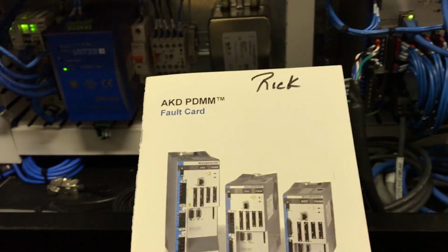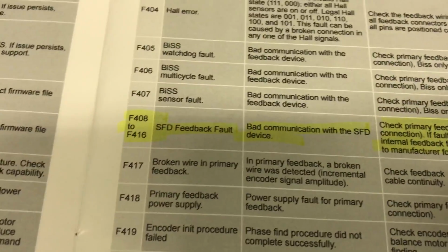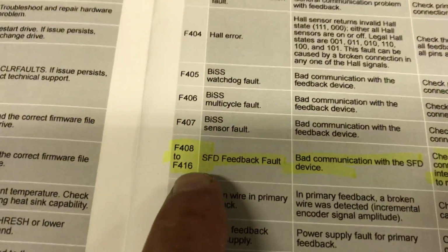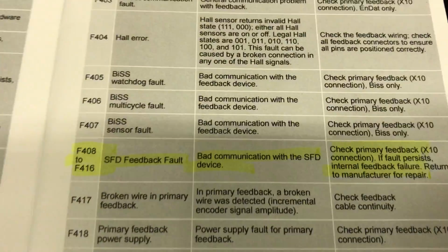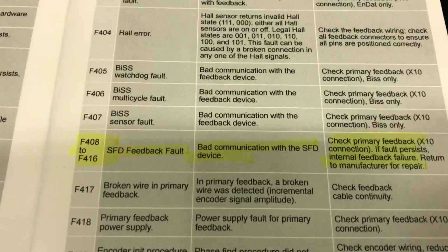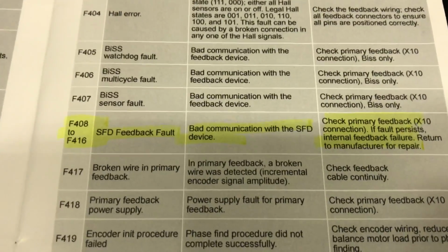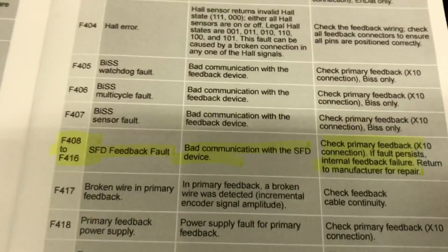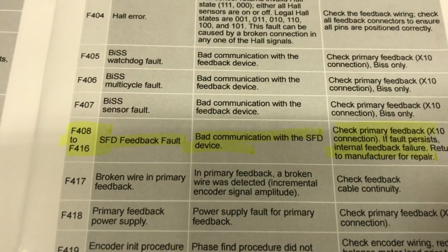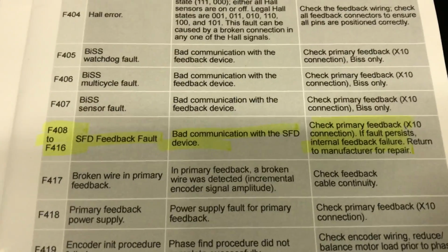So if I come to this book, you can look this up online as well. And I look it up, I've highlighted it here, F415 is in this range. It's a smart feedback device fault. That's the encoder fault, bad communication with the SFD smart feedback device, which is the encoder on this machine.